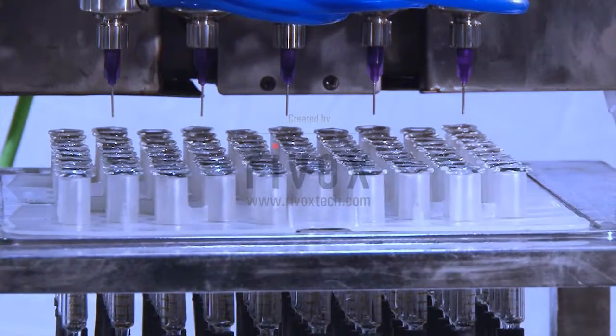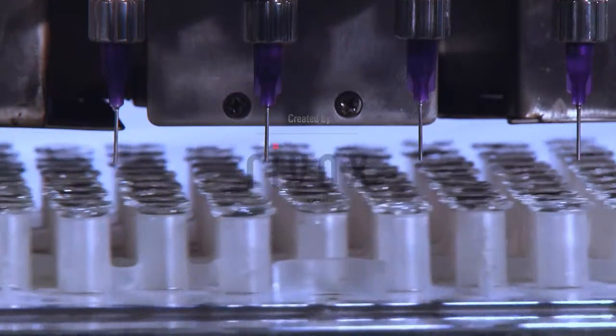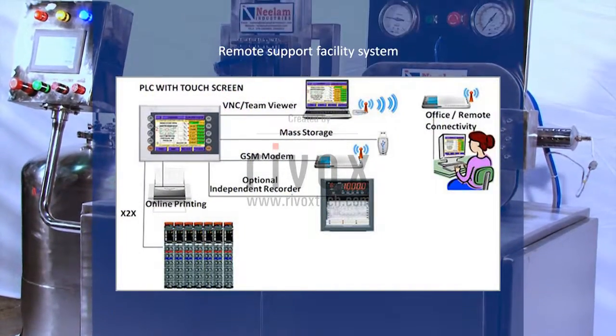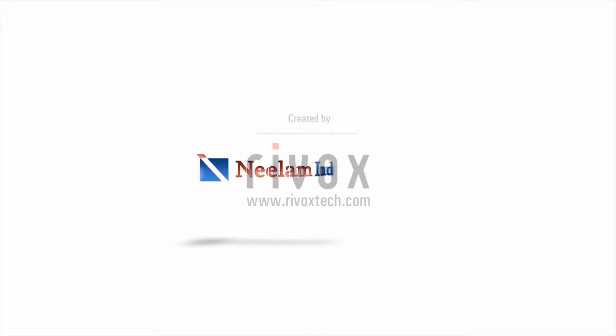It has higher filling accuracy with an output capacity of 6,000 syringes per hour, while no change parts are required for filling within the range of 0.2 to 5 milliliters. The system is designed to provide after-sales service remotely via an online remote support facility.